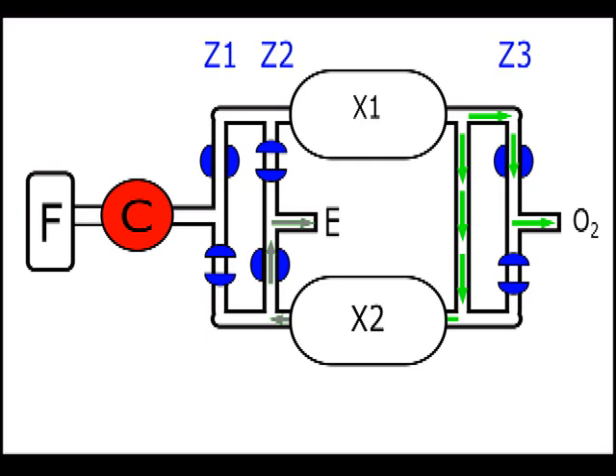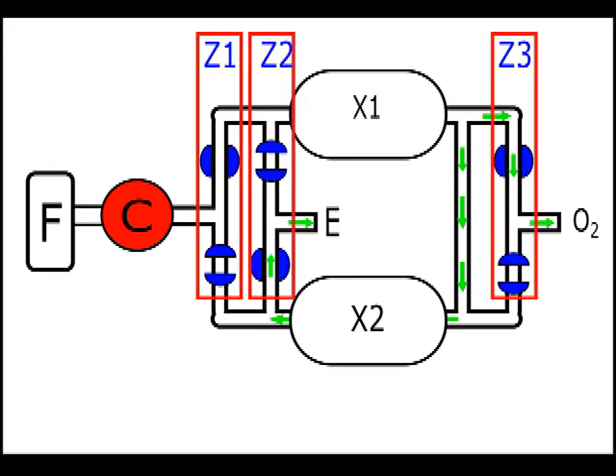As expected, after a certain period, the X1 cartridge sieve becomes clogged by nitrogen molecules, so performance begins to decline. To guarantee continuous operation, a control circuit activates three double solenoid operated valves labeled Z1, Z2, and Z3, which swap the connections of the X1 and X2 cartridges.